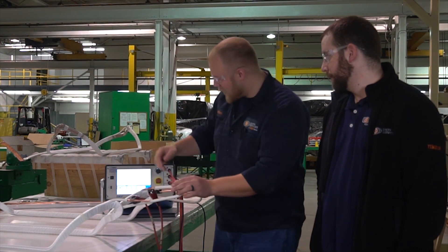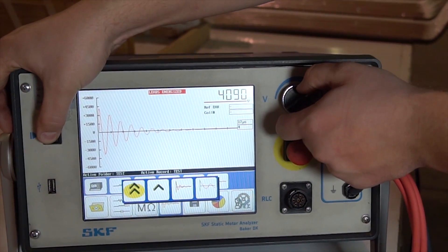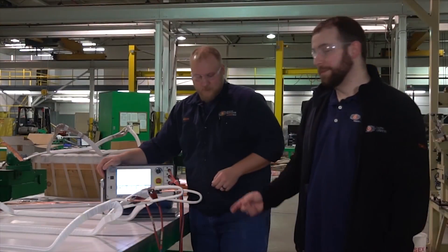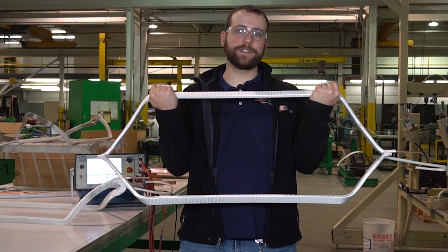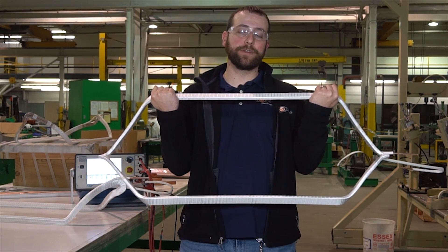I'm here with our technician, Allen. We will now do some electrical testing to verify our coil and the integrity of our insulation system. First, he'll connect his leads to the first coil. We will then adjust the voltage to the appropriate level. Once he has the proper voltage, he will reference this waveform. We will then move his leads to the second coil, perform the same tests, and the waveform should match. This is our final product — fully insulated, electrically tested. Insulation integrity has been verified and it is ready to install into a stator.